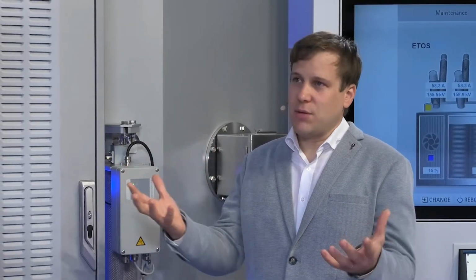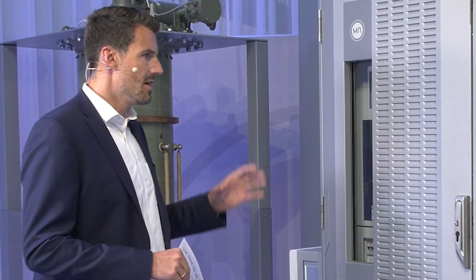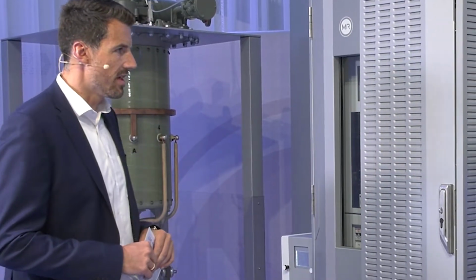You're absolutely right, Stefan. Any kind of sensor that either outputs an analog value, a classical digital on-off value, or that can deliver the information per Modbus RTU, all of these sensors can easily be integrated into ETOS. So we're fully open to include any kind of information that is available at the power transformer and to make use of the data and make it available for the customer. That's for sure a big benefit and a real value for our customers out there.